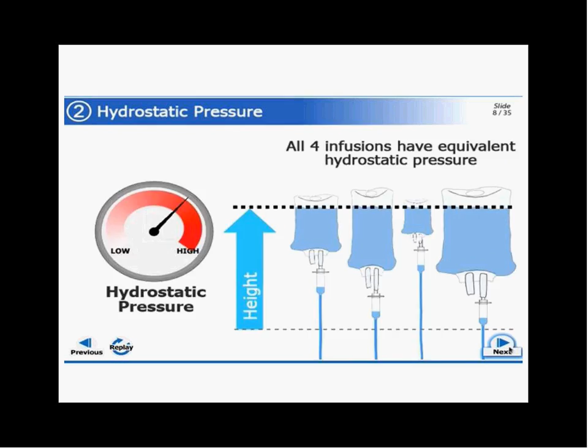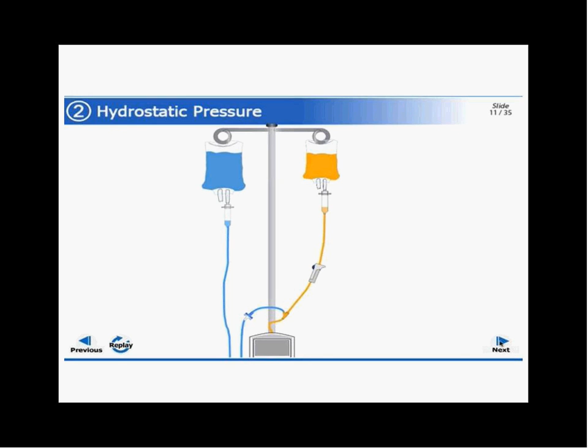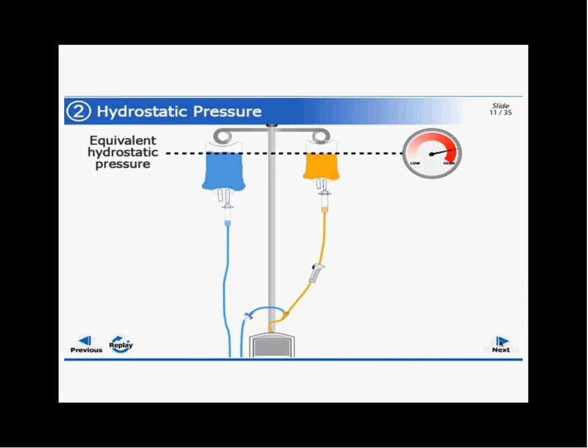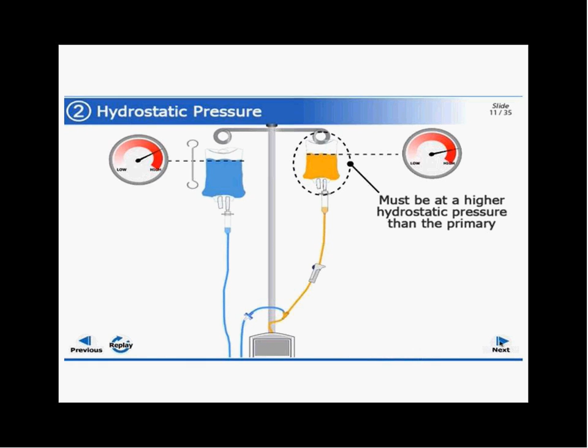We then apply this underlying theory, the physics behind everything, to why we have to do some setup tasks when administering a secondary infusion, such as lowering the primary IV bag. If the secondary IV bag is hung with the hanger so that the top fluid in both bags is at the same height, or equivalent hydrostatic pressure, the fluids in both bags will flow concurrently, that is, at the same time. The fluid in the secondary IV bag to infuse first is at a higher hydrostatic pressure than the primary IV bag. This is why we use a hanger over the primary IV bag, so its pressure is less than the secondary infusion.